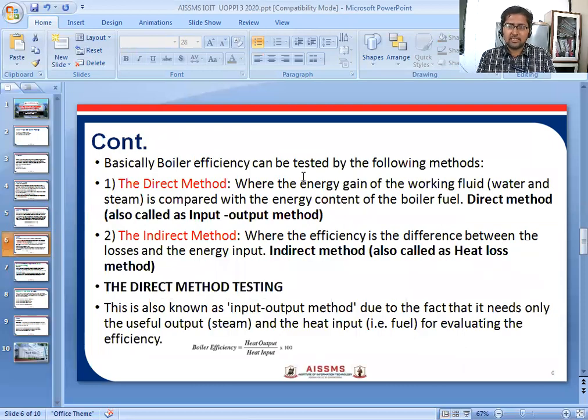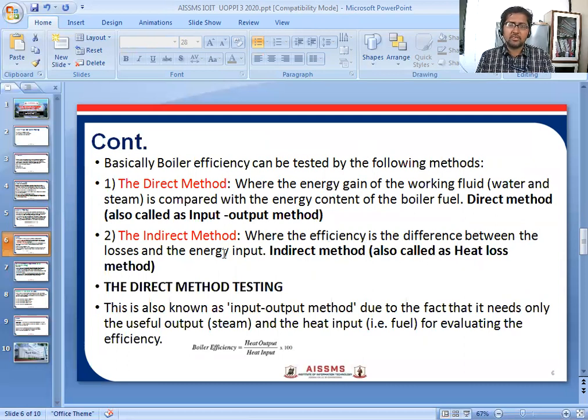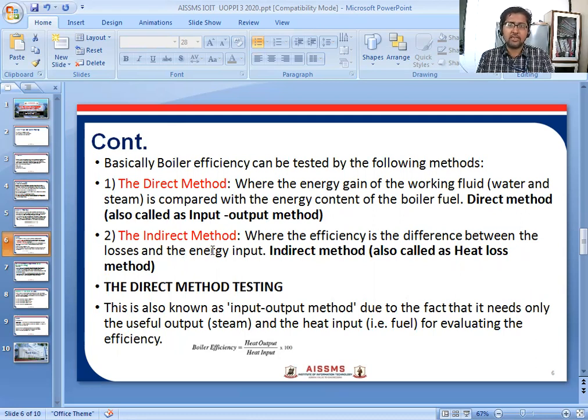Boiler efficiency can be tested by two methods: the direct method and the indirect method. In the direct method, the energy gain of the working fluid — water and steam — is compared with the energy content of the boiler fuel. In the indirect method, also called the heat loss method, efficiency is the difference between losses and energy input. Direct method calculation is simple: boiler efficiency equals heat output divided by heat input into 100.